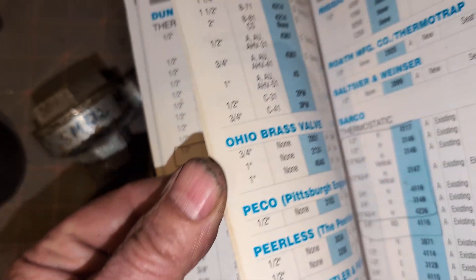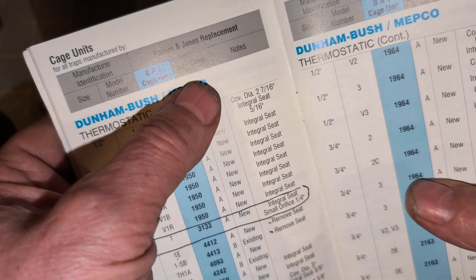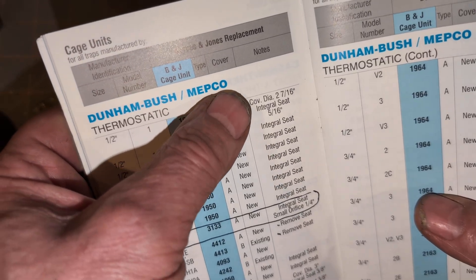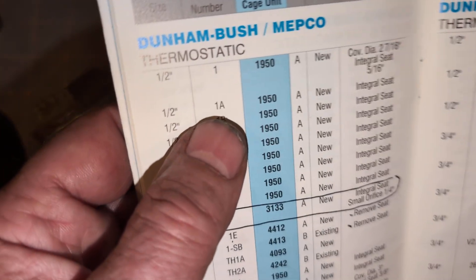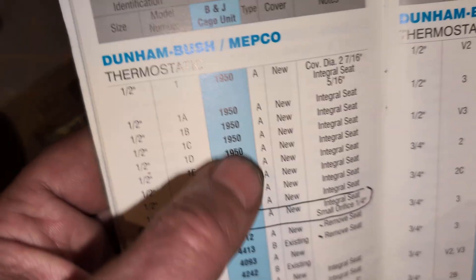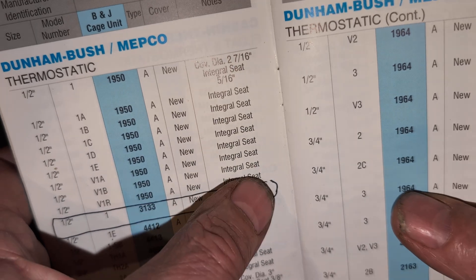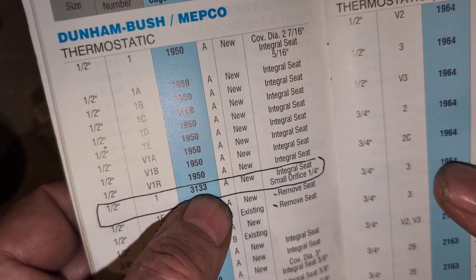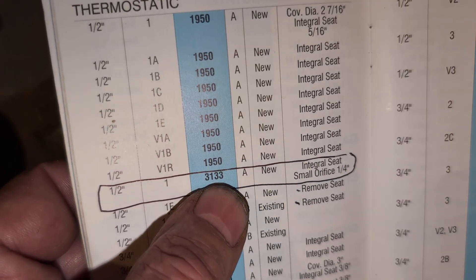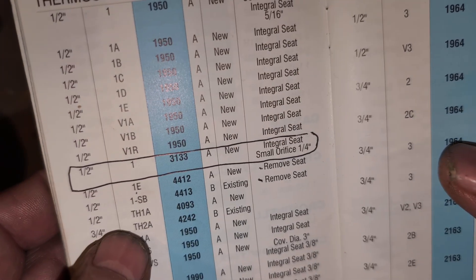This is the Barnes & Jones handbook. There are multiple traps available from various manufacturers — we turn to Dunham Bush. So you've got a Dunham, a Dunham Bush, and a MEPCO. They're all about the same. MEPCO is still in existence — the Marshalltown Engineering Products Company. If you have a 1A, 1B, 1C, 1D, or 1E, they all use the same internal component and all need a new cover. They all have integral seats.